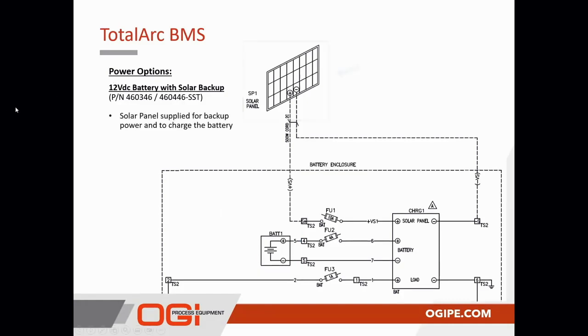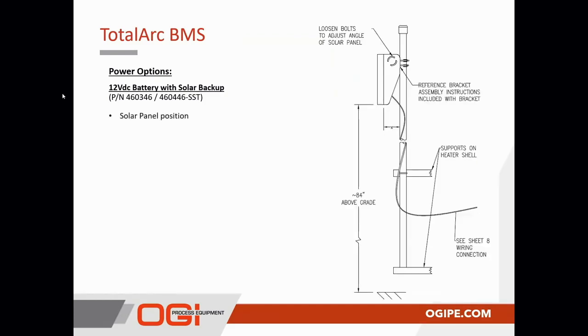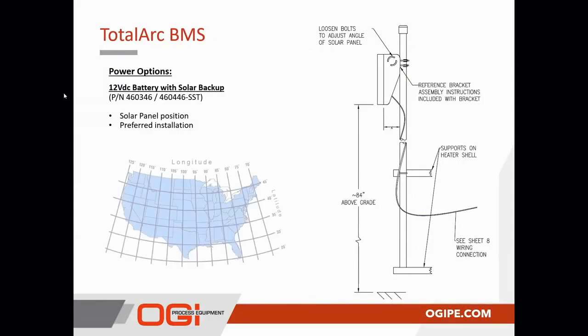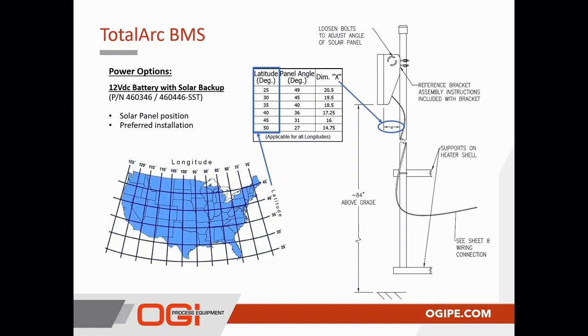Backup power for the battery and the charging for the battery is provided through a solar panel. It's a 50-watt solar panel and a power converter that transforms the voltage from the solar panel to the battery to keep it charged. To get the best performance out of the solar panel, ensure the panel is facing the southern sky. Adjust the angle of that solar panel based on the latitude of the site, which we're showing here. The same chart and information is also provided in the BMS manual.